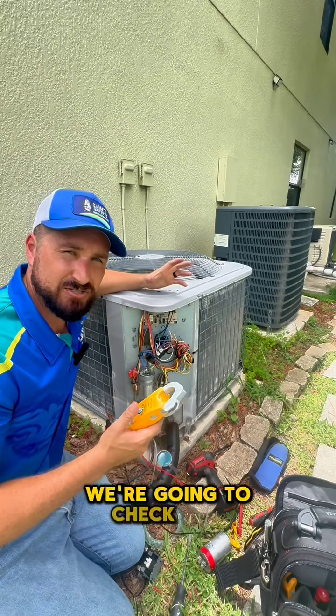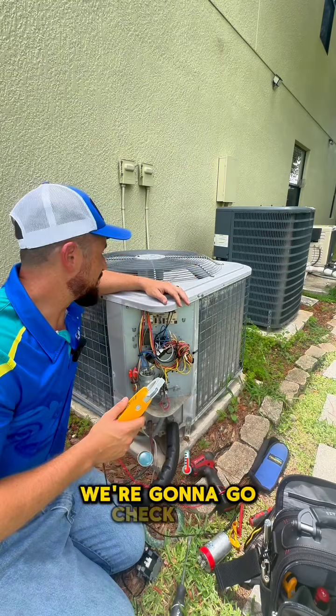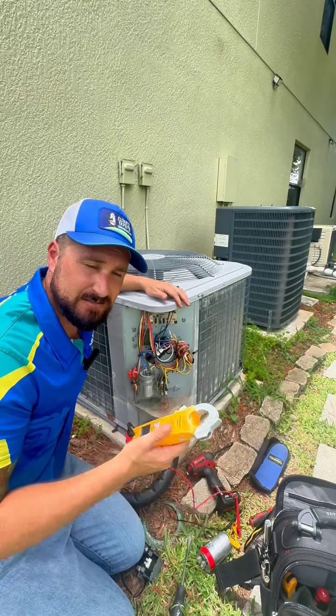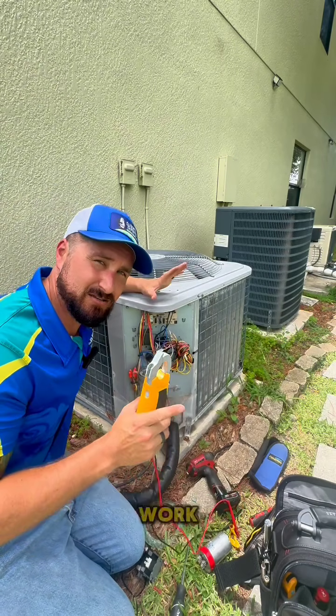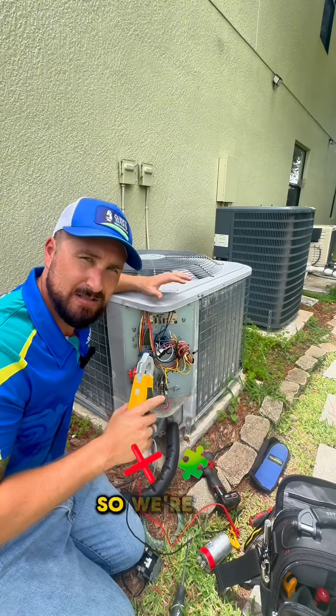We're going to go inside. We're going to check the amp draw of the blower motor. We're going to go check the temperature split to make sure we have the right delta T. We're going to check humidity. We're going to even check the ductwork because that's attached to this AC system. So we're not part swapping.